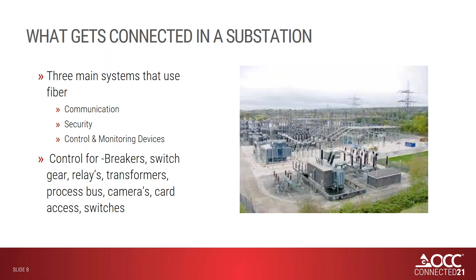So we know there are over 55,000 substations in the US and growing. And again, conversion to fiber has been happening rapidly over the last 5 to 10 years. So what do we know about this? We know there's a high level of EMI at these sites, which could cause a problem if you're using copper cabling for data transmission. They're exposed to extreme and harsh environments, such as high and low temperatures, dust, wind, hail, lightning strikes. And these substations are typically unmanned and rely on SCADA for remote supervision and control. For that reason, they're subject to sabotage from terrorists, possibly, or other criminals.